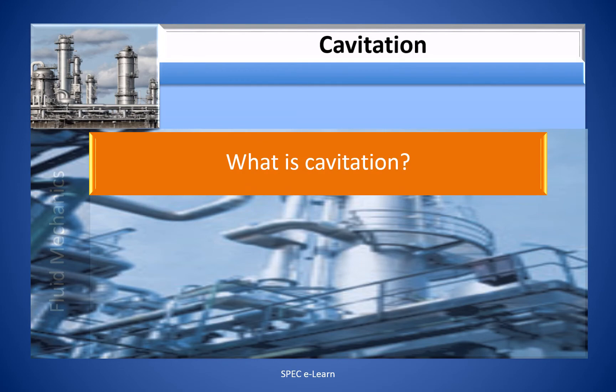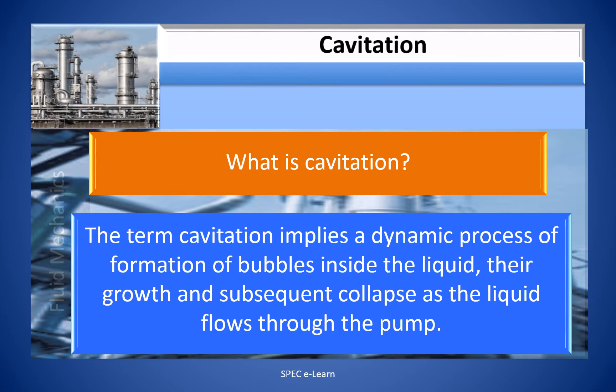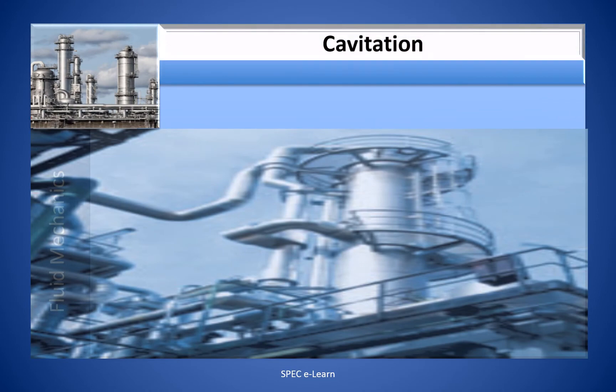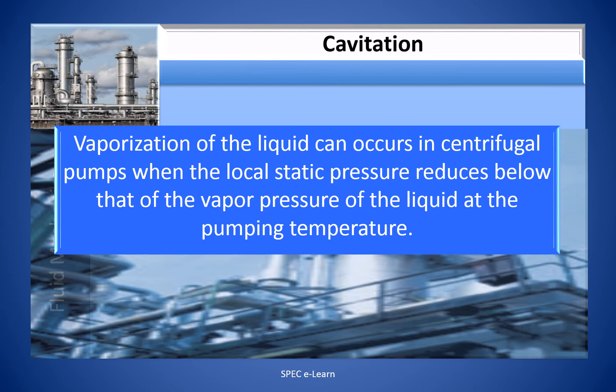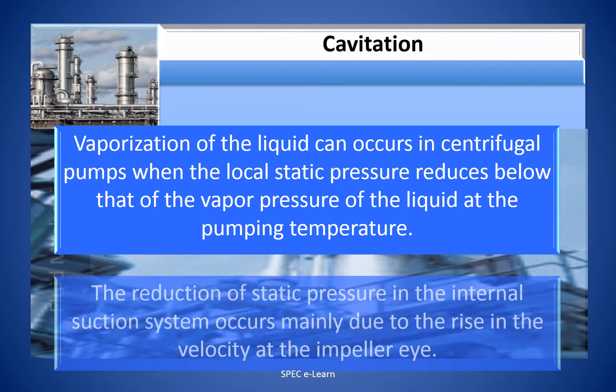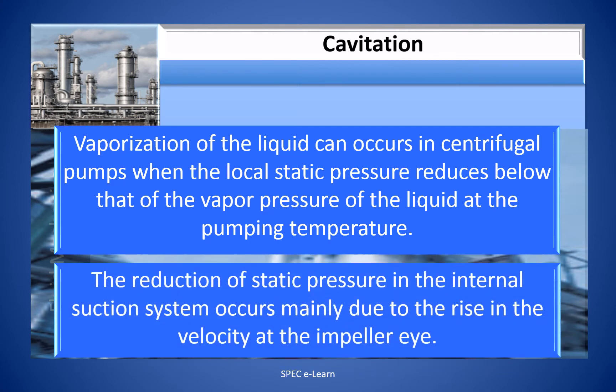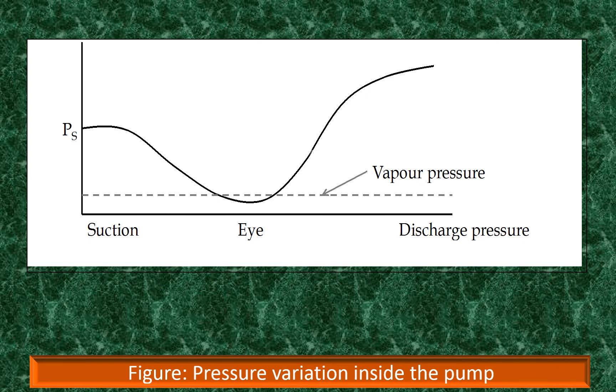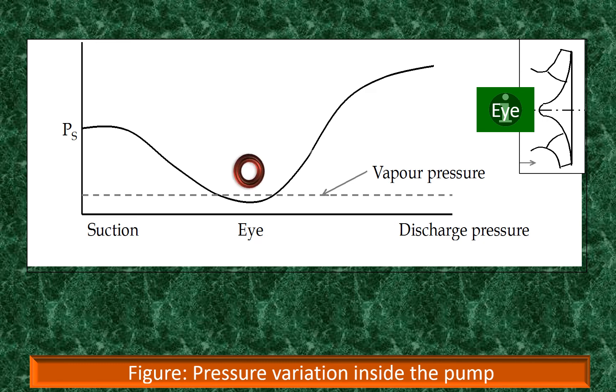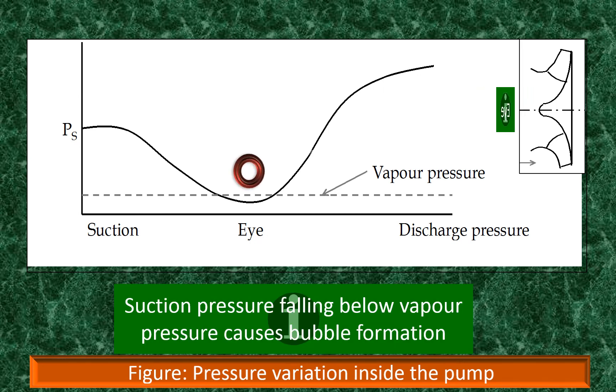What is cavitation? The term cavitation implies a dynamic process of formation of bubbles inside the liquid, their growth, and subsequent collapse as the liquid flows through the pump. Vaporization of the liquid can occur in centrifugal pumps when the local static pressure reduces below the vapor pressure of the liquid at the pumping temperature. The reduction of static pressure in the internal suction system occurs mainly due to the rise in velocity at the impeller eye. As shown in this figure, the suction pressure decreases as the liquid approaches the eye of the impeller, and just at the eye the pressure falls below the vapor pressure, causing bubble formation.